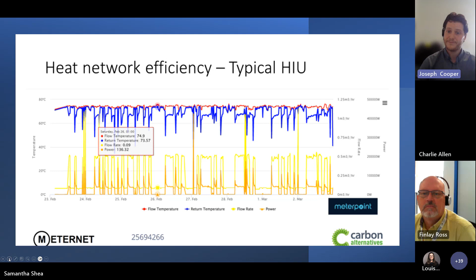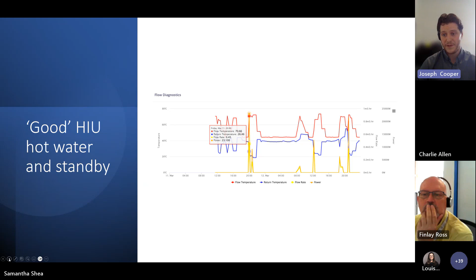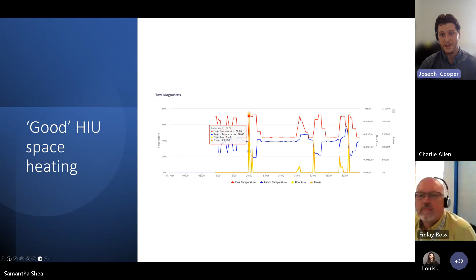If we compare that slide to an example of a good HIU for the hot water and standby, you can see the differences quite visually there. You've got a flow temperature of 70 degrees and a return temperature of 26. So that delta T is absolutely huge, and that in turn makes the whole system far more efficient and less expensive to run. And a good HIU in terms of space heating as well. So again, you've got a high flow temperature and a much lower return temperature, so a much higher delta T, again making the system much more efficient. So comparing those graphs with a typical example of an HIU within our apartments is night and day, really. You can see the difference visually there.